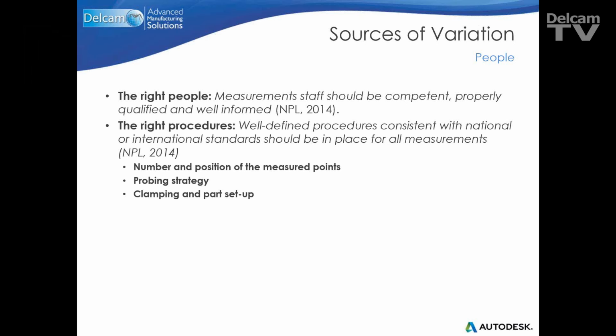So that's one thing, is, you know, why do we clamp components? We clamp them so they don't move. If we're applying or exerting any force, obviously if you're using optics, lasers, you're not applying force, but if you're using contact systems, you're applying force. So we clamp it to make sure that the component isn't moving, even within this 40 microns that we've just talked about. And so it becomes very important to look at that clamping strategy. Some companies I know will go to the full extreme of placing a torque tolerance onto their clamping, so that they're not actually over-stressing or distorting the component by any clamping forces that they're using.